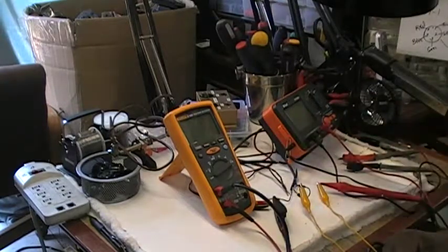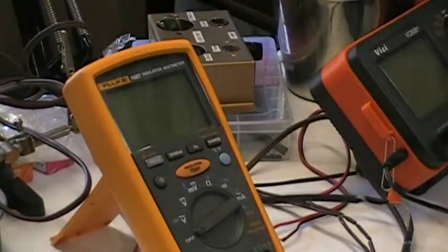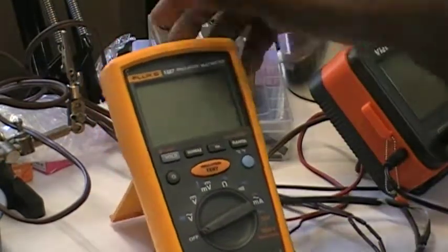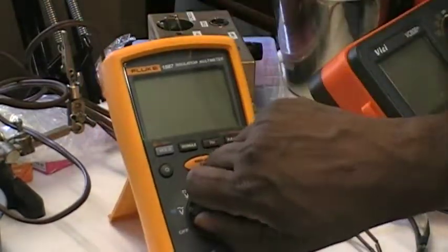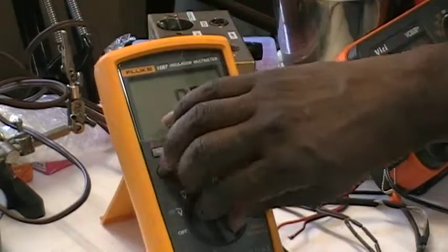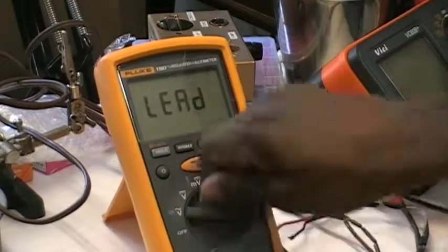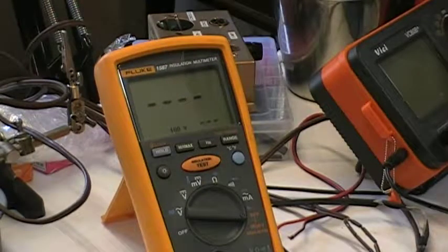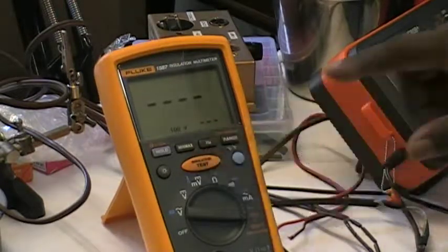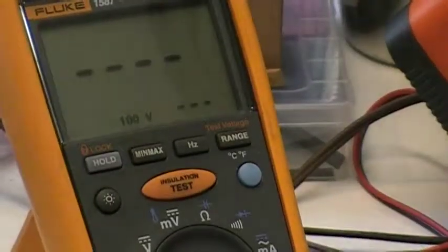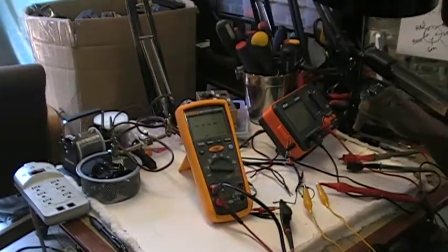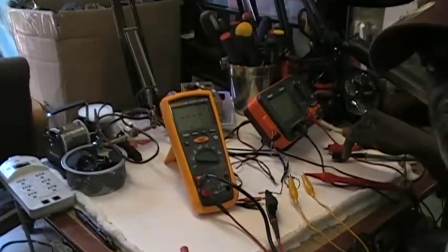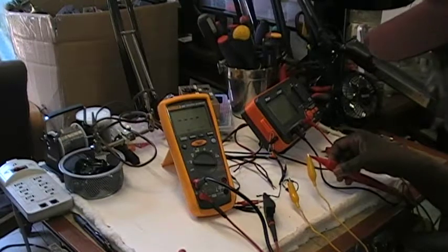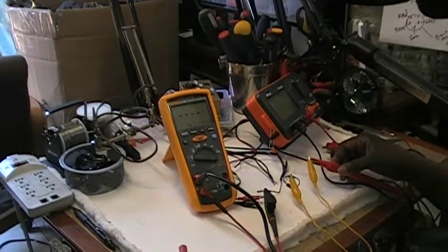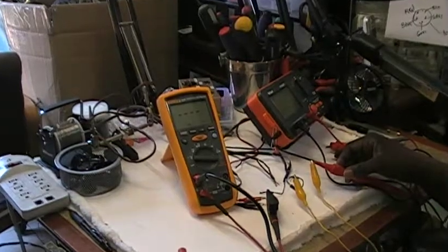Turn it on. Now this is known to be bad. I have it set at 100 volts. Now I have on my probe a test button that I can use, so I'm going to use the test button on the probe instead of pushing the insulation test button; it does the same thing. Let me move you back here so you can see what comes up on the meter when I push the button.